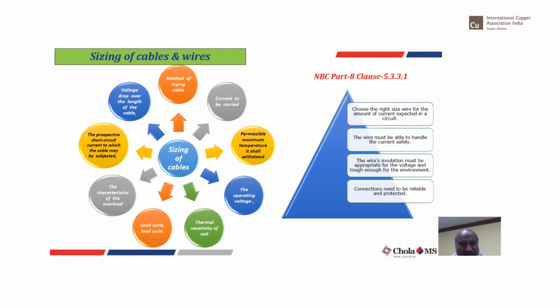So please take all these factors into account. Don't just go only by the chart, saying this 300 square mm aluminum will carry 300 amps, or 200 square mm will carry 200 amps. This comes down drastically depending on the way that you lay the cables. NBC also talks about all of these things.